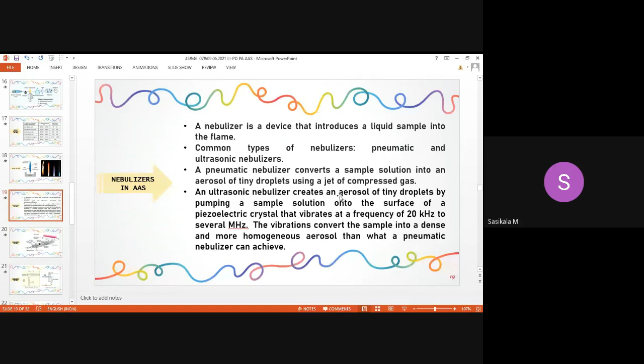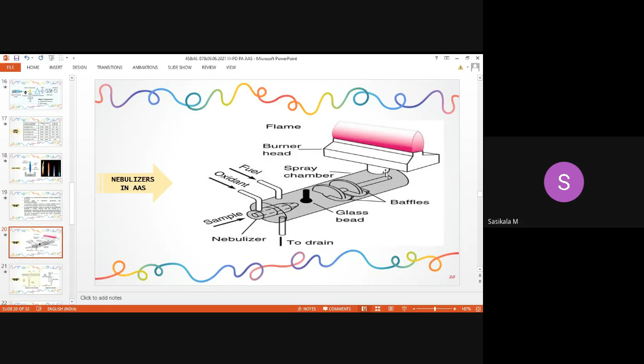You can see here, this is the nebulizer. Okay, so sample is taken through the nebulizer, where fuel and oxidants are applied. With the pressure of oxidant and fuel itself, the sample will be taken by the nebulizer and passed to the flame. Okay, and the extra sample will be drained. You can see it will be going to the waste. Whatever sample required will be passed to the flame.